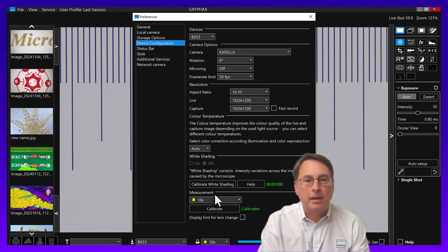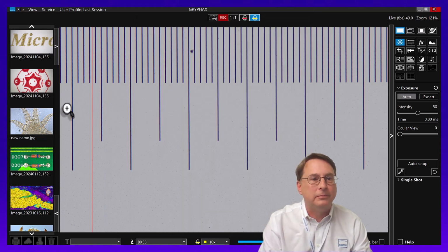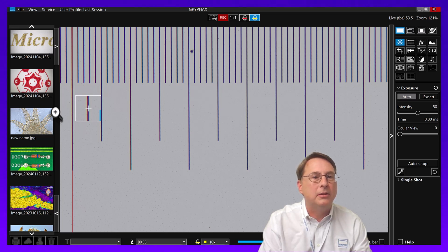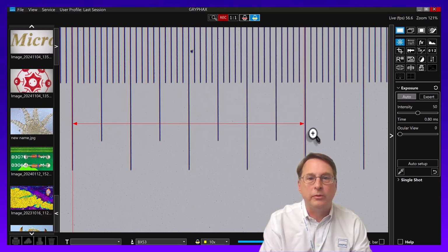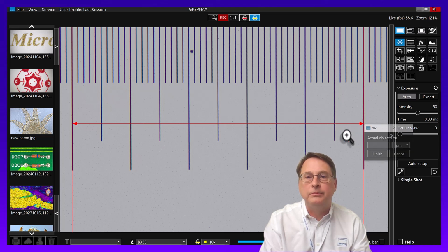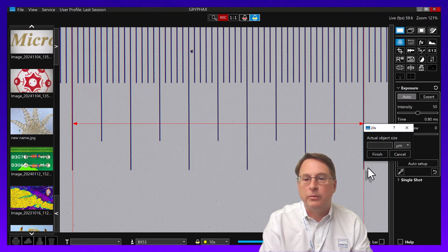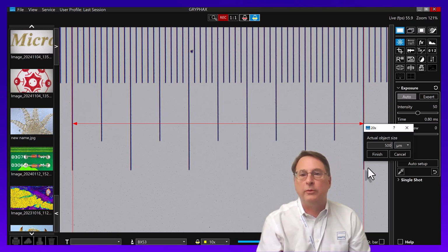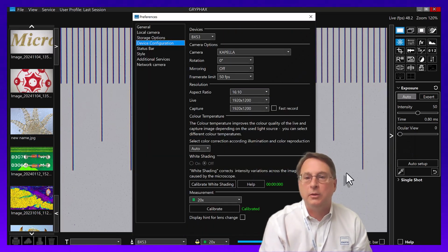I'll do one more. Here's 20x. I'll choose 20 from my menu, then click calibrate. And just as before, as soon as I can start to see the thickness of the lines, I like to go right edge to right edge. But you can go right to right, center to center, left edge to left edge. So I'm going to try to go right edge to right edge, 100, 200, 300, 400. Right about here, let's say. Okay, so 1, 2, 3, 4, 500 microns. Makes sense since we were at 1,000 before. Finish. And you can keep on doing this with a 40x or a 60x or whatever objectives you have.